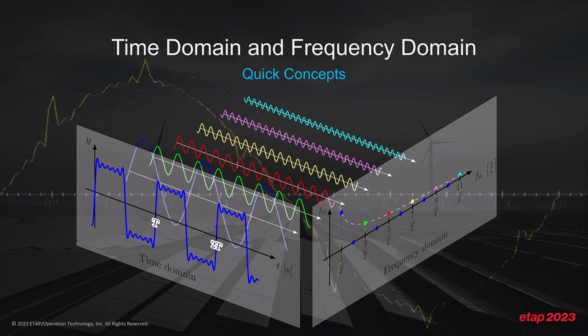Due to the ever-increasing number of nonlinear loads on our power distribution system, the existence of harmonics nowadays is inevitable. As a result, voltage and current waveforms are rarely sinusoidal. Harmonics is a form of waveform distortion that occurs in circuits that contain semiconductor-based electronics such as LED lighting, SMPS, electronic ballast, computers, robotics, test equipment, etc. These nonlinear loads impose higher frequency sine waves on the system, which result in more power lost in the form of wasted heat. The excess heat produced by harmonics can have a detrimental effect on the power system.